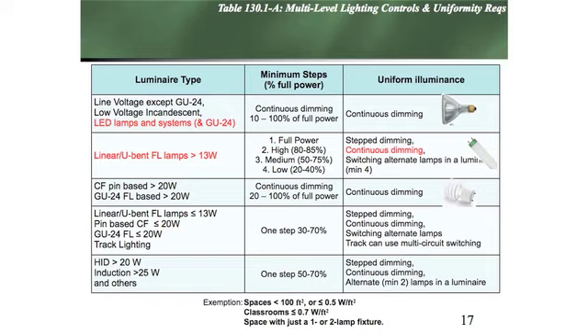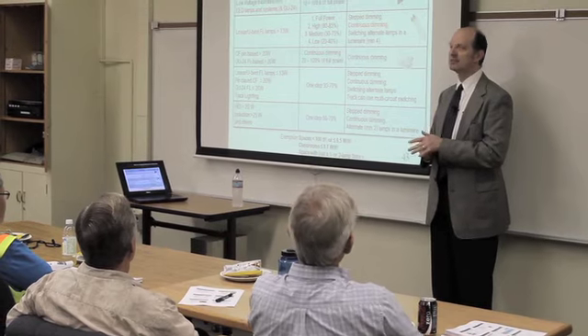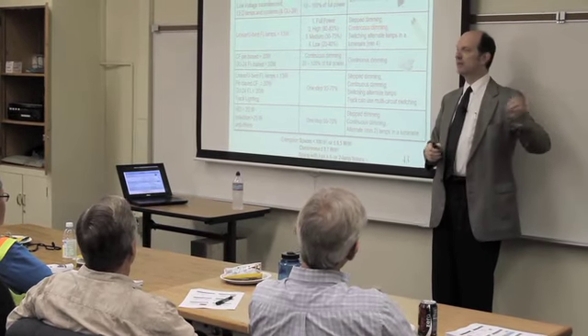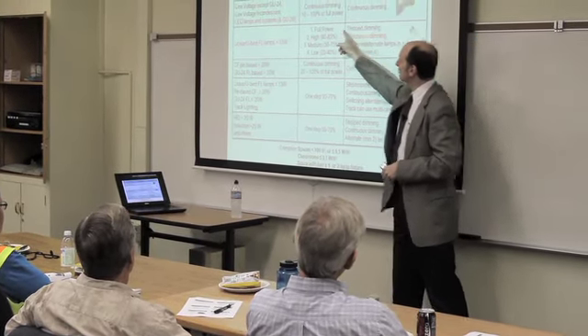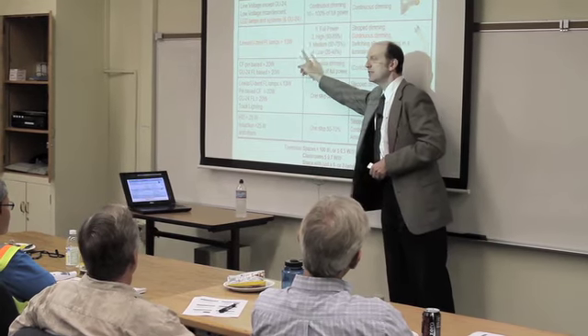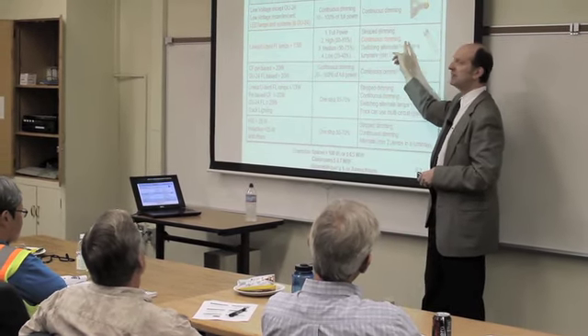But then you get over here to high. For all the fixtures, you've got to be able to get from 100% to 80-85%. How are you going to do that? The answer is it's not going to be switches on the wall. What this is really doing is pushing anybody using standard fluorescents into continuous dimming.